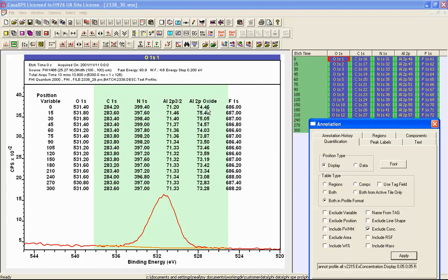And indeed, this shows up quite nicely how the oxide peak does move as a consequence of the etch cycle. This is occurring as the film of oxide is reduced, then the position of the peak is adjusting, and that might be something you would be interested in having a look at to see what this actually means in terms of the measurement. Is this chemical state change, or does this represent some type of charge compensation that is functioning in a slightly different way with a different film thickness of oxide on a metal?